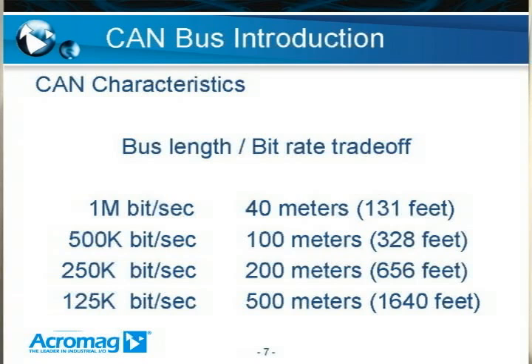The maximum length of the CAN bus is dependent on the bit rate being used. A one megabit per second bus can have a maximum length up to 40 meters, while a slower implementation such as 125 kilobits per second would be able to go up to 500 meters.